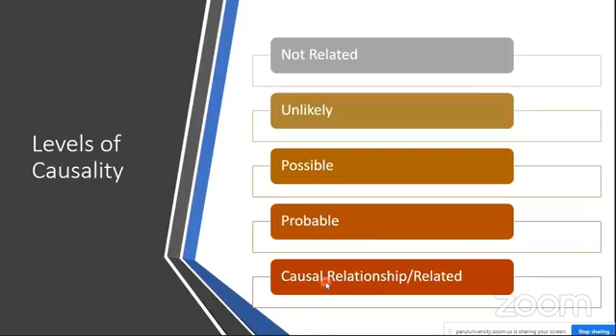So if you want to say a particular adverse event is not related, or the particular medical device is not the reason for that adverse event, then you need to actually evaluate these criteria. It is not necessary that all the criteria should be met at the same time, but depending upon your device or the particular treatment you are considering, and the complexity of the device, you can have one or two or more, or some of these criteria need to be established to say that the particular event is not related to the medical device. So, what are those?